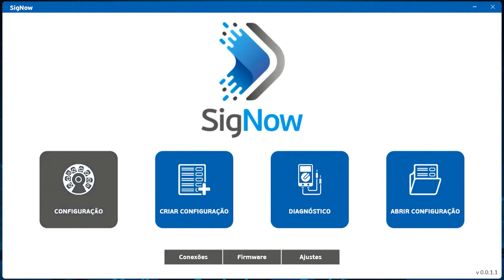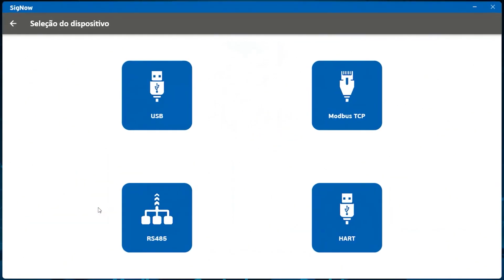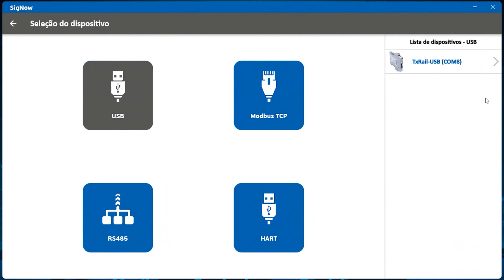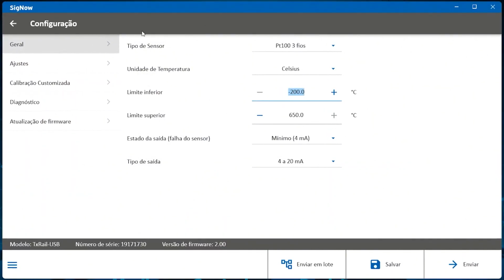In it, there are the following communication modes: USB, Modbus TCP, RS485, and HART protocol. I'm going to use this one, the USB interface. In this mode, the device already appears as connected. TX Rail USB is connected to COM8 port. I'm going to click here. The following options will be displayed: General, Tuning, Custom Calibration, Diagnostic, and Firmware Update.